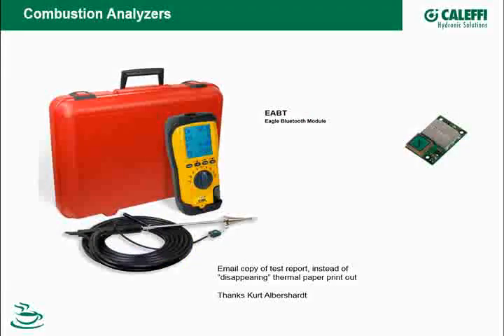I was talking to one of my contractor buddies this week and said, well, you know, what are you using for equipment these days? What do you got going on for your combustion analyzers? And this is a picture of the meter that he uses. And what was interesting is he's got the Bluetooth module for it. So when I had the Bacharach meter that I've used for years, it had a little thermal printer that came with it. So every time I would leave a job, I would leave a copy of the report from the combustion analyzer on the job site, right in a little envelope with the boiler, and then take a copy with me. So if down the road somebody said, well, that boiler was never set up right, blah, blah, blah, I had a record of it. You know, it was dated on there, had date stamp and everything on it.